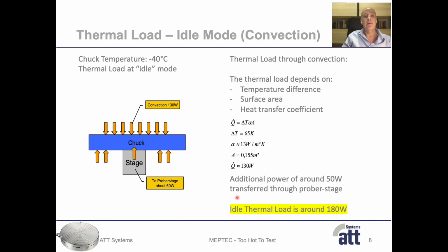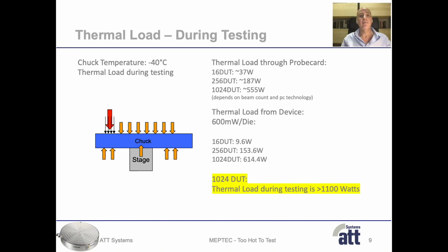Additionally, there are another 50 watts from the stage. This gives us a total thermal load of around 180 watt at -40 degrees in standby mode. So this means that we need to dissipate around 180 watt just to keep the chuck temperature at -40 degrees C. No testing, no needle contact, just to keep the temperature stable at -40 degrees C. So we have around 180 watt in idle or standby mode.